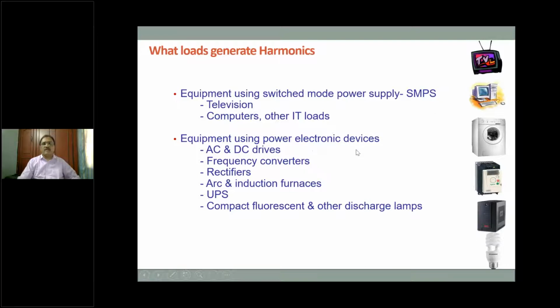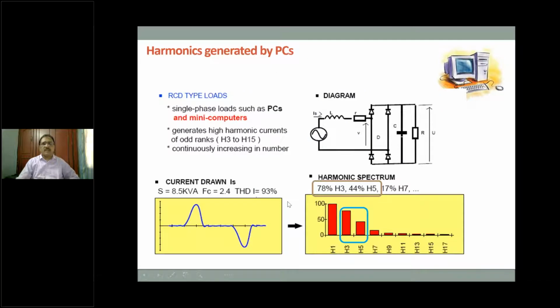Equipment using power electronic devices like AC, DC drives, frequency converters like VFD, like I told you, rectifiers, arc and induction furnaces, UPS, compact fluorescent and other discharge lamps. All these are generators of harmonics. All these in different shapes generate different orders of harmonics, and as we go, we will understand what these are. So, like I mentioned to you, all PCs which you use, your laptop or your PC at home or a smart TV, almost 100% of its current is harmonic current.